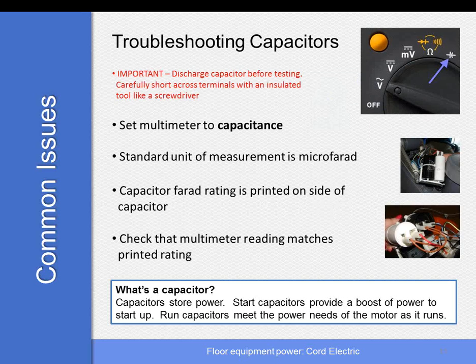To check a capacitor, you'll flip your multimeter to the capacitance setting, which is going to be a vertical line with a curved line to the right. It's also important to discharge your capacitors before you test, and the easiest way to do that is to take an insulated tool like a screwdriver, and you're going to short out the two leads. You might see sparks, you might not. Be careful when you do this. You don't want to burn yourself.